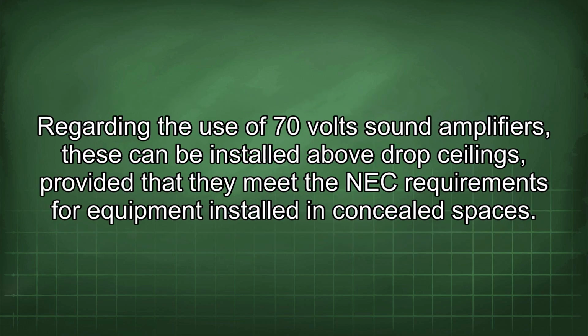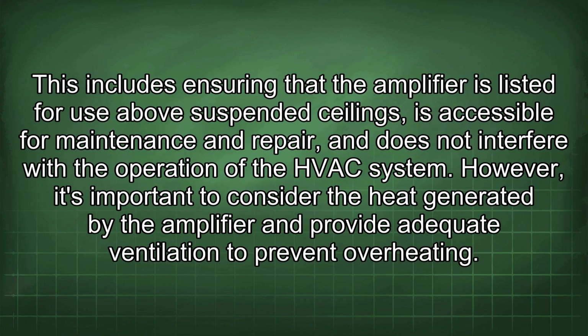Regarding the use of 70-volt sound amplifiers, these can be installed above drop ceilings provided that they meet the NEC requirements for equipment installed in concealed spaces. This includes ensuring that the amplifier is listed for use above suspended ceilings, is accessible for maintenance and repair, and does not interfere with the operation of the HVAC system.